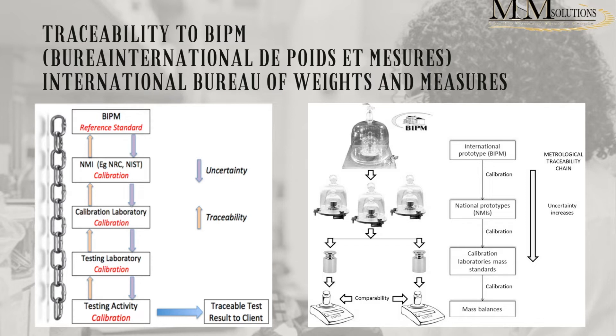The easiest and most straightforward way of getting traceability is to use an accredited calibration laboratory, which provides traceability for your measurement result — whether for your balance, temperature, or any other measurement instrument — traceable to BIPM or to NIST. Or when you're using a certified reference material from an accredited producer, those would be accredited with ISO 17034 to produce CRMs.